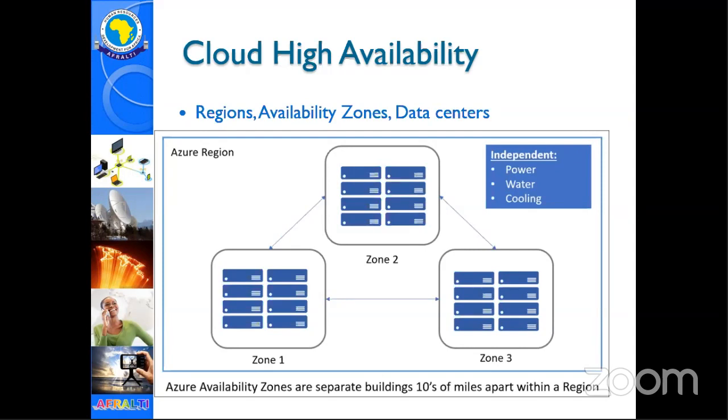That comes straight from the Kenya Power substation that serves that region. I think it's in Embakasi. So straight from Embakasi to that data center, no other customer in between. And the reason for that is because if there are many customers along the way, then there are instances where it will be shut down for maintenance, then there'll be faults and all that. And then, of course, the power won't be guaranteed. So independent power, independent water, and independent cooling.